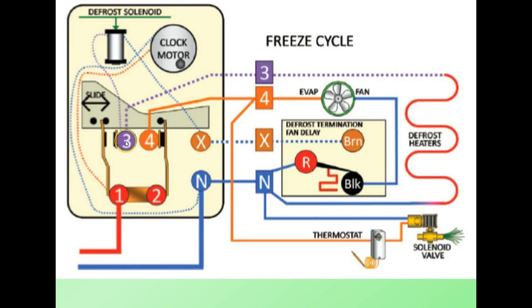In the freeze cycle, we have the solenoid valve open and powered up, we have the evap fan powered up, the defrost heaters are off, the defrost solenoid has no power so it is sitting there idly. We now have a freeze cycle happening and we're waiting for the defrost clock to tell things to hit the defrost mode.